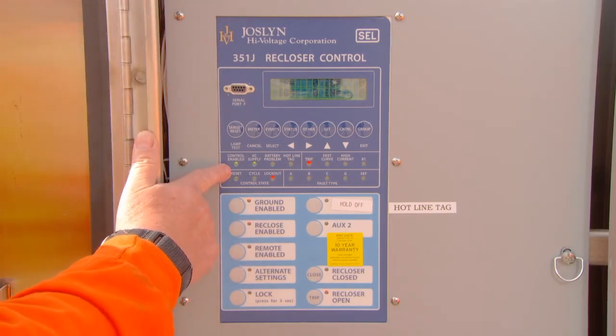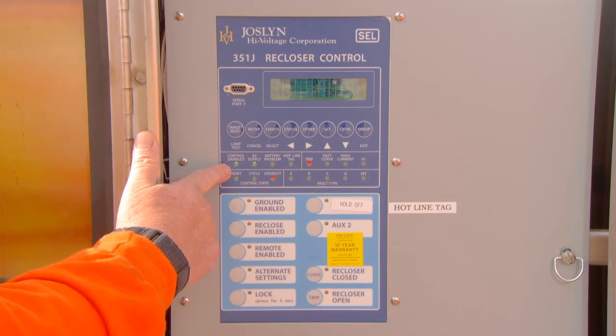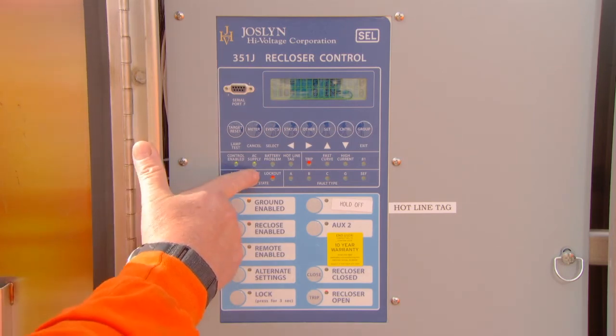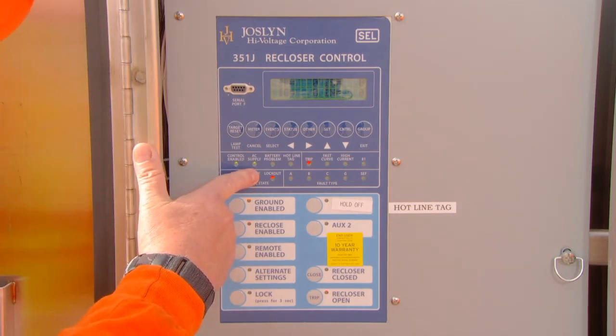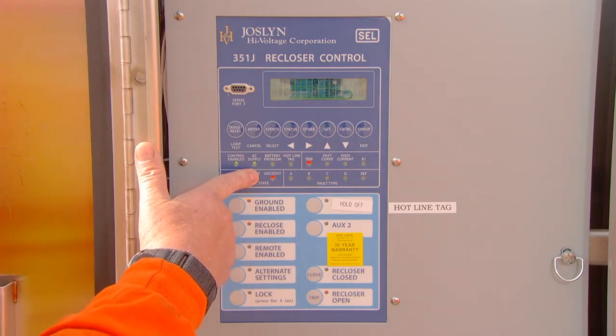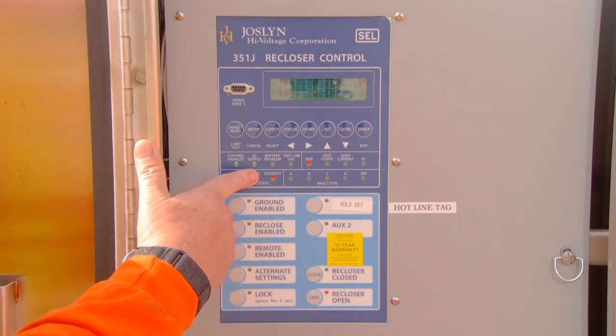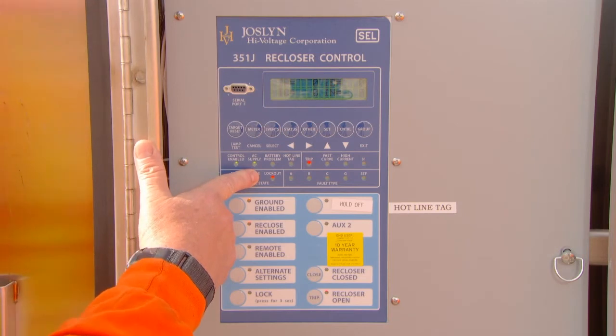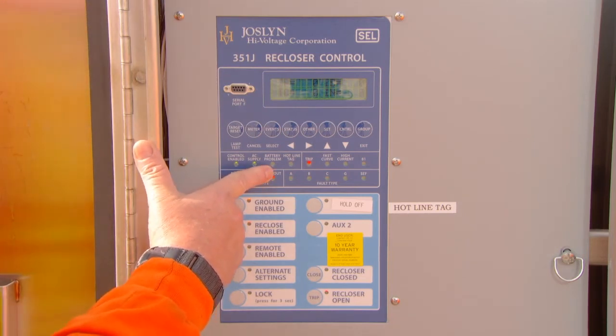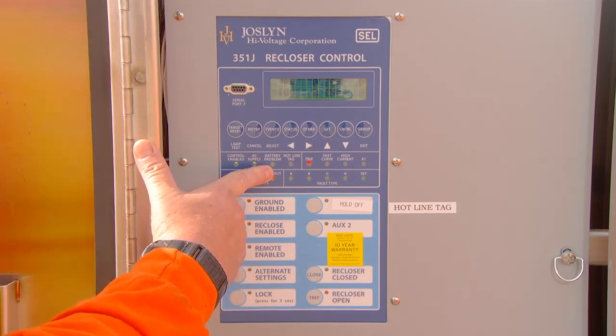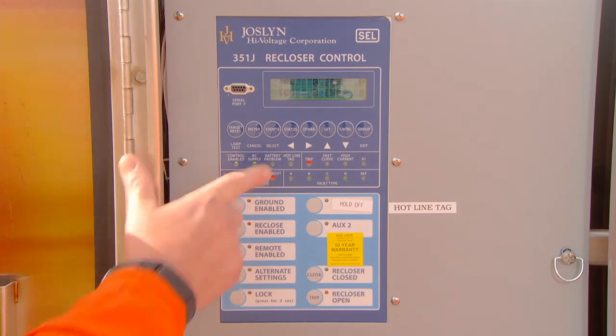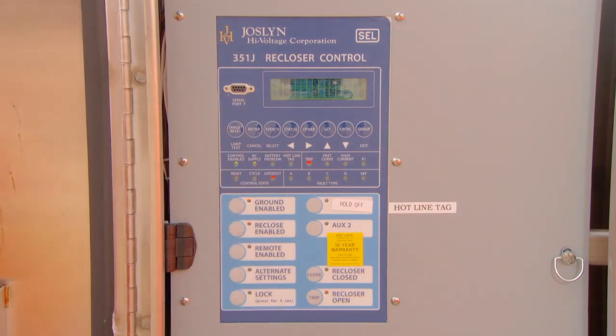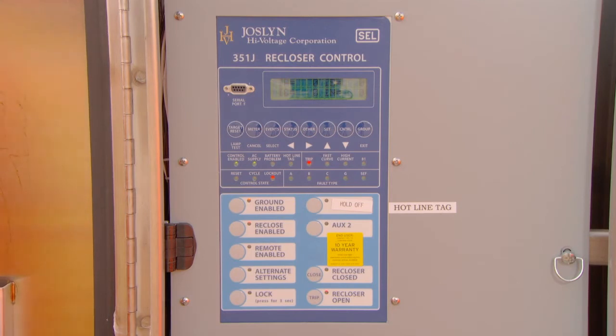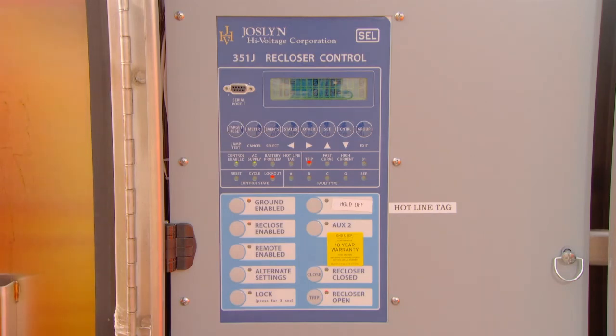First, we have Control Enabled. The green light tells us the control is enabled and ready to function. Next is AC supply, which is also green. This means the unit has an AC supply. Should a battery problem occur with this unit, such as the battery depleting itself under a loaded condition, the battery problem light will turn red. This unit performs its own internal tests once every 24 hours.